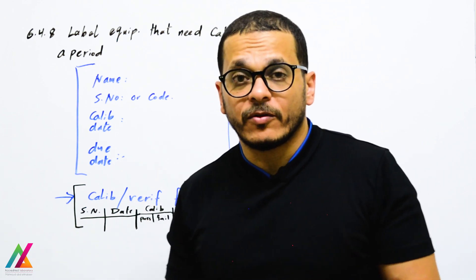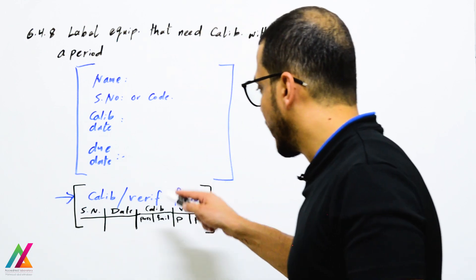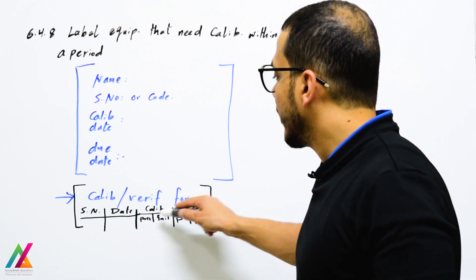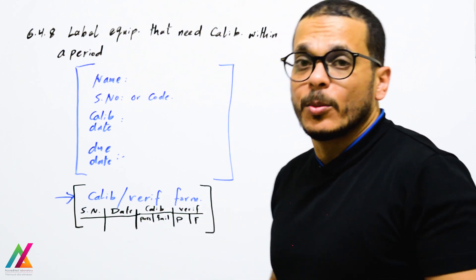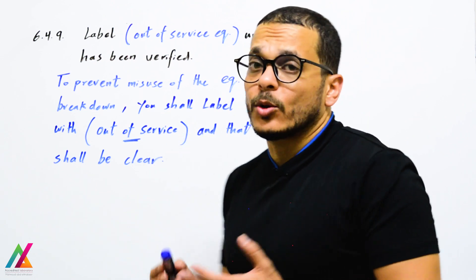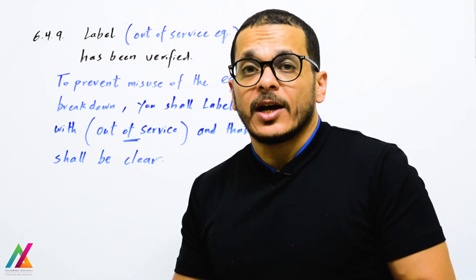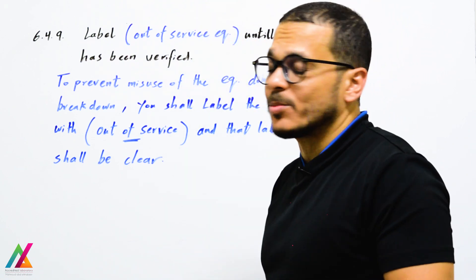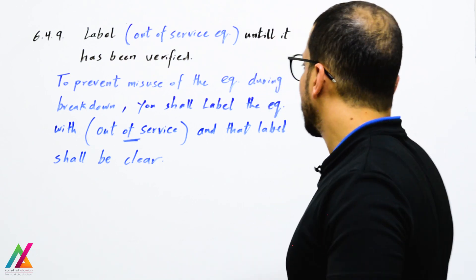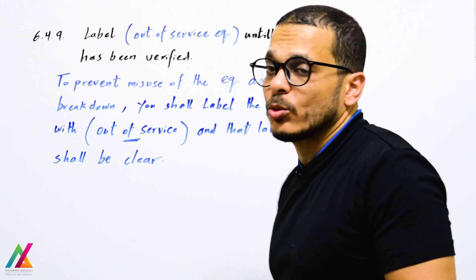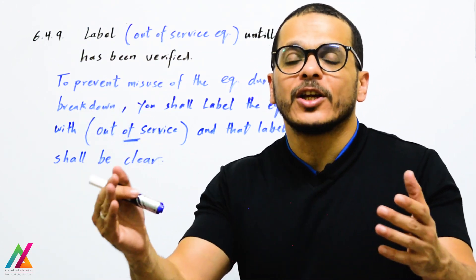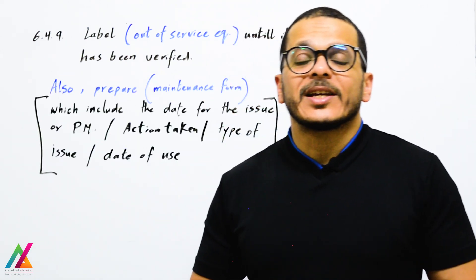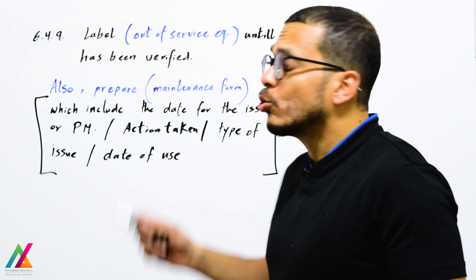Prepare a calibration and verification record form showing serial number, calibration date, verification date, and whether calibration and verification passed or failed. Equipment that is under maintenance or in breakdown shall be labeled 'Out of Service' until it has been verified — this prevents misuse during breakdown or maintenance. The 'Out of Service' label must be clearly visible to everyone.